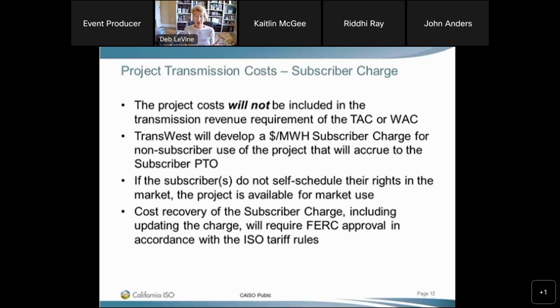For those not intimately involved in how the ISO develops the TAC and WAC: for all participating TOs, we determine their high voltage transmission revenue requirements and their low voltage transmission revenue requirements. If they are load serving entities, we look at their gross load for the previous regulatory period, add up all the costs, and divide that cost by the gross load. Some participating TOs — Harry Allen, El Dorado, Citizens, Sycamore, Penasquito, Transbay Cable, among others — are not load serving entities but have a transmission revenue requirement. So we come up with a dollar-per-megawatt-hour number, and that's what everybody gets charged for the TAC and the WAC.